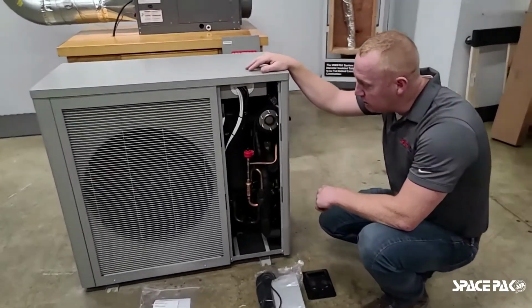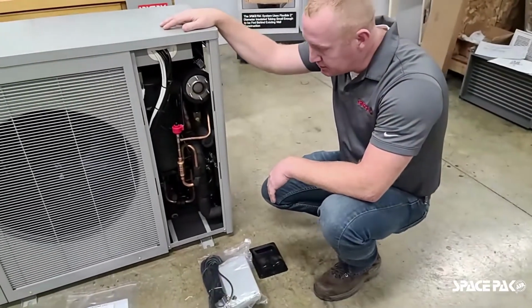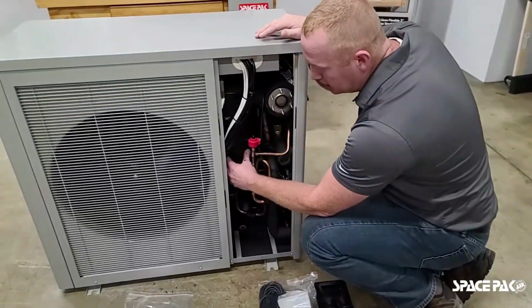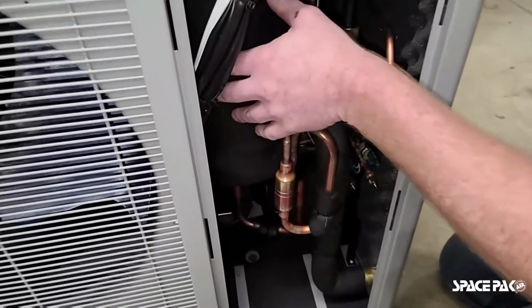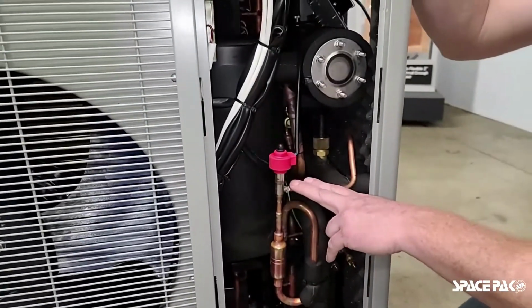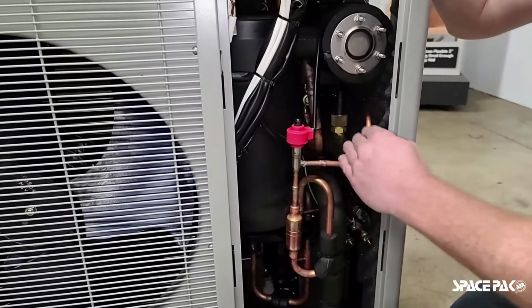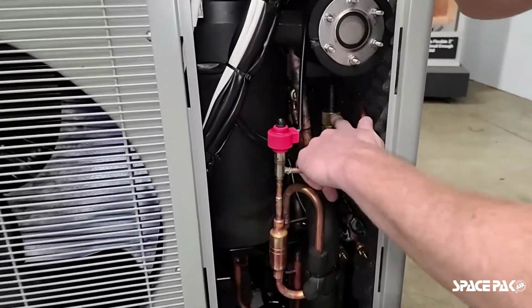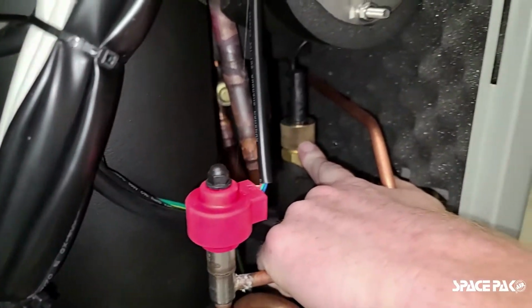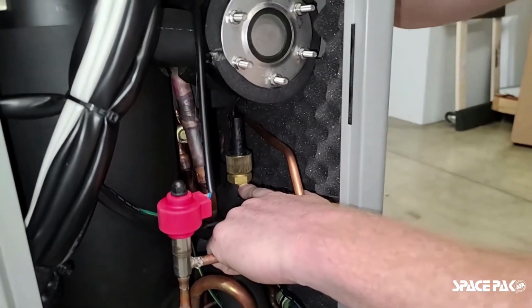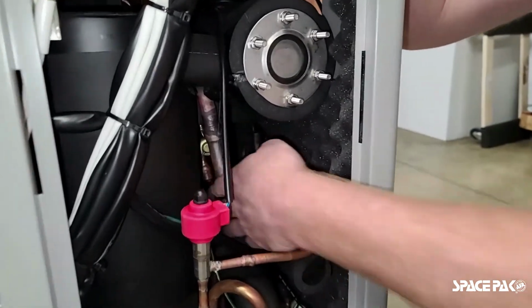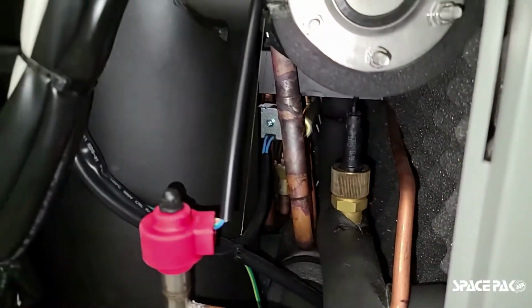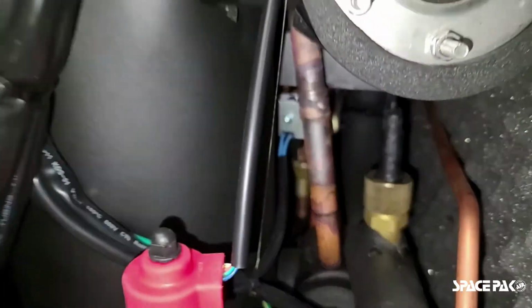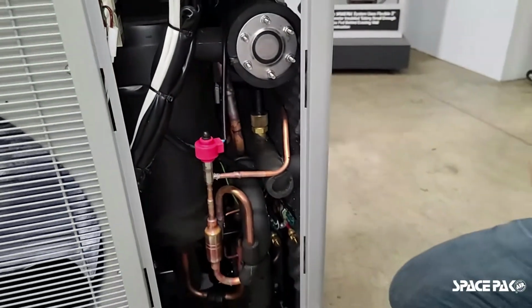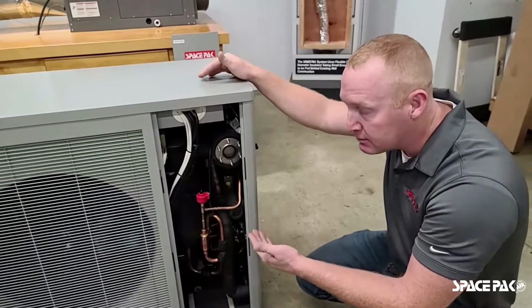So bringing us back to a few more of the components within our SIM Series inverter heat pump, we've got our Mitsubishi inverter compressor located here, center of the unit, and the electronic refrigerant valve right here, front and center. A little bit further in the back, we mentioned it earlier, we have the flow switch. The flow switch is going to prove before we can actually start the unit up. And then even further behind that, a little bit harder to see, would be our 3-way valve, right? The valve that would make that adjustment, far in the back there where those two blue wires are attached. That's going to make the difference in deciding whether we're going to be running our system in heating mode or cooling mode.